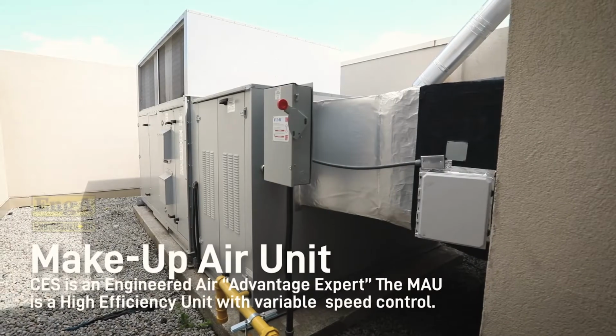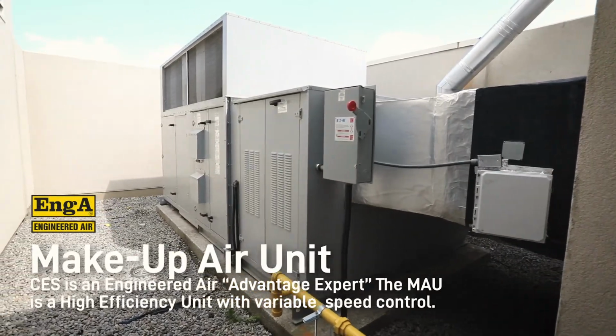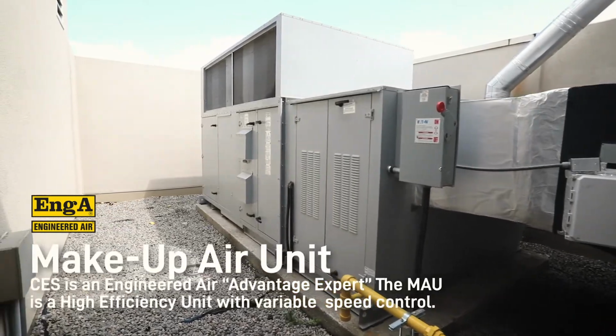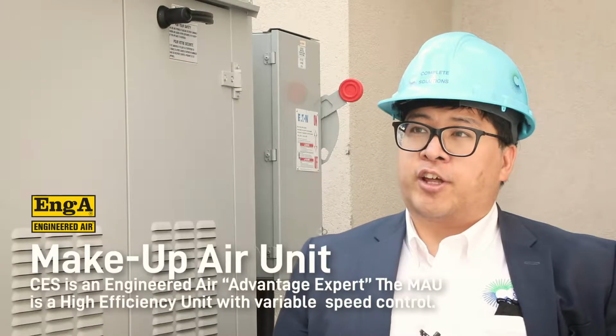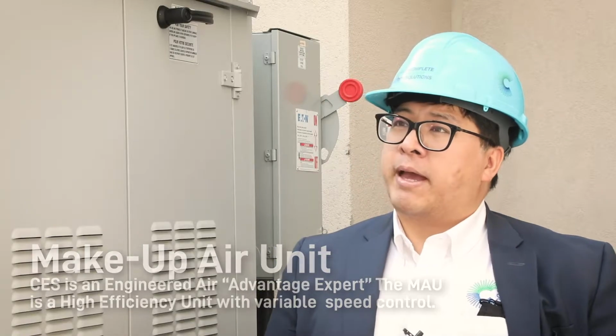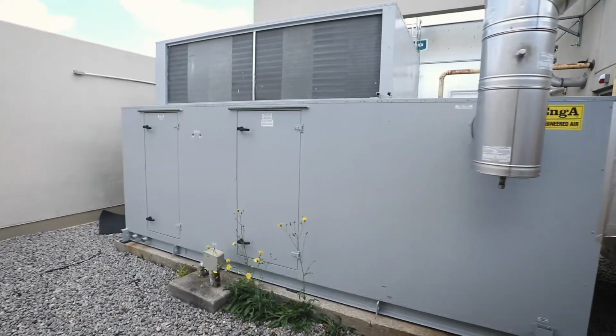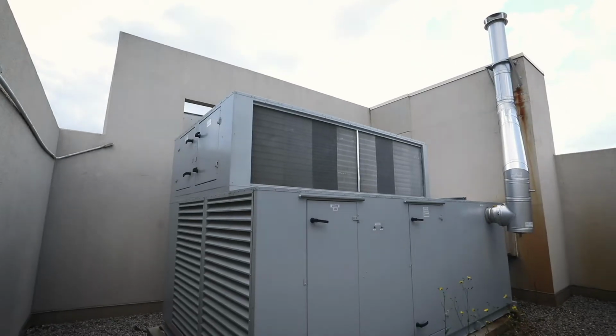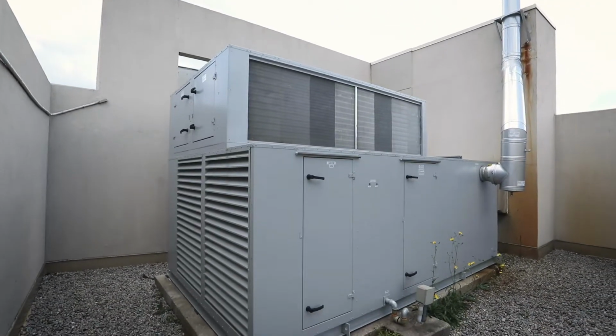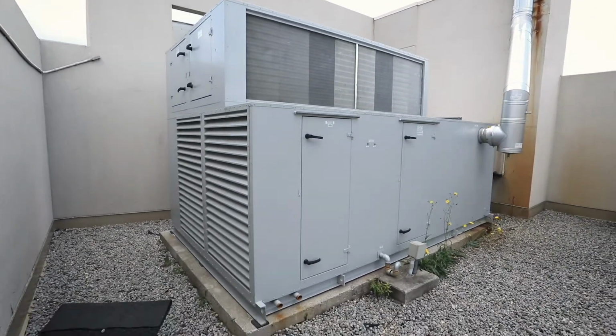This is a new makeup air unit that we installed just this year. It's a high efficiency unit with variable speed control, far more efficient than a constant volume unit. This here is a package unit as well with a cooling section on top, far more efficient than a separately packaged unit with a remote condenser. This unit can be expected to last a long time and generate energy savings for the building that exceed the cost of the actual project.